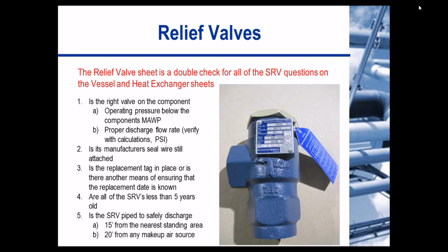Now, the relief valve sheet is a double check for all safety relief valve questions on the previous inspection sheets. Some of the questions that you're going to see: is the component operating below the component's maximum allowable working pressure, and is there proper discharge flow rate? These are things that you can verify with calculations. Also, is the manufacturer's seal wire still attached to the relief valve? Is there a tag in place, or is there another means of ensuring that the replacement date is known? If these things are missing, the relief valve is essentially considered out of service.